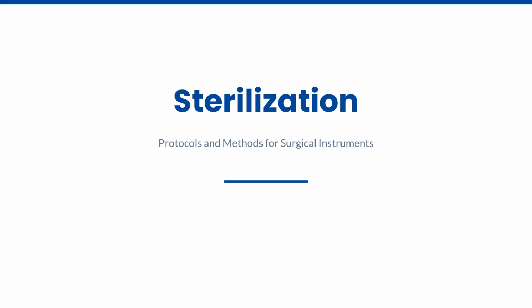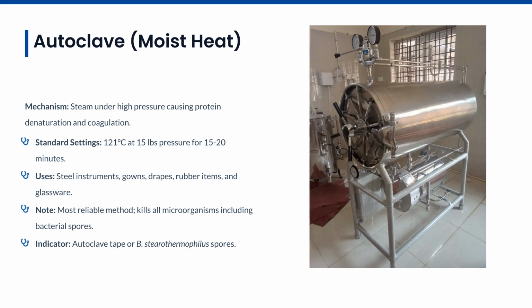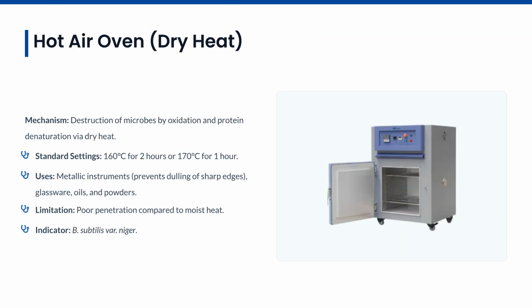Next, let's briefly review the sterilization protocols and methods for surgical instruments. Autoclave, or moist heat, sterilization is the most reliable method. It uses steam under high pressure at 121 degrees Celsius for 15 to 20 minutes, killing all microorganisms, including bacterial spores. The hot air oven uses dry heat to destroy microbes by oxidation. Standard settings are 160 degrees Celsius for 2 hours.